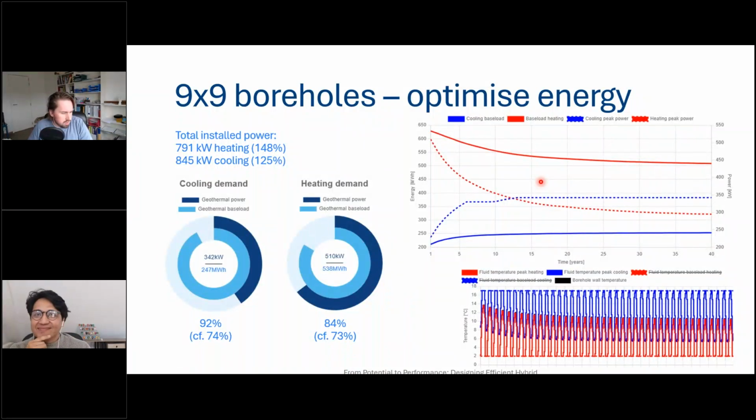So the way this method works is it will optimize not every hour but every month. So it will take the hourly profile. It will make a load duration curve for every month in the simulation period, which is quite a lot. And then in every month it will say, well, I want to stay between the temperature limits.